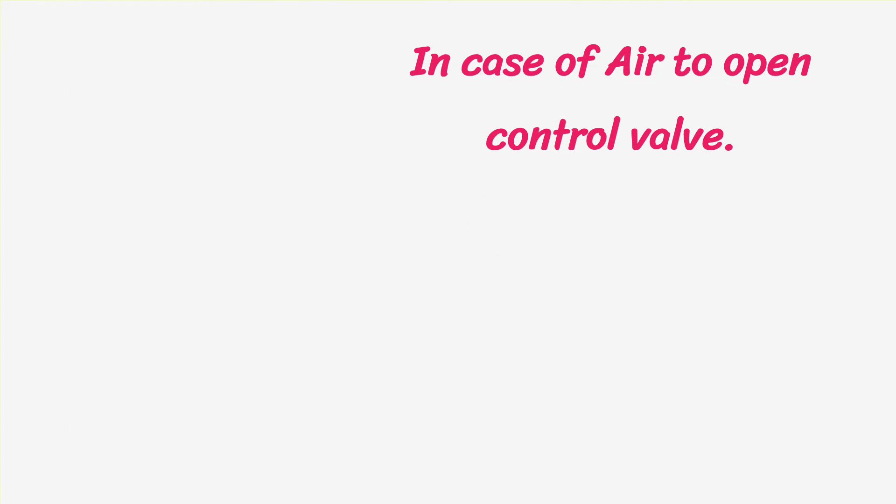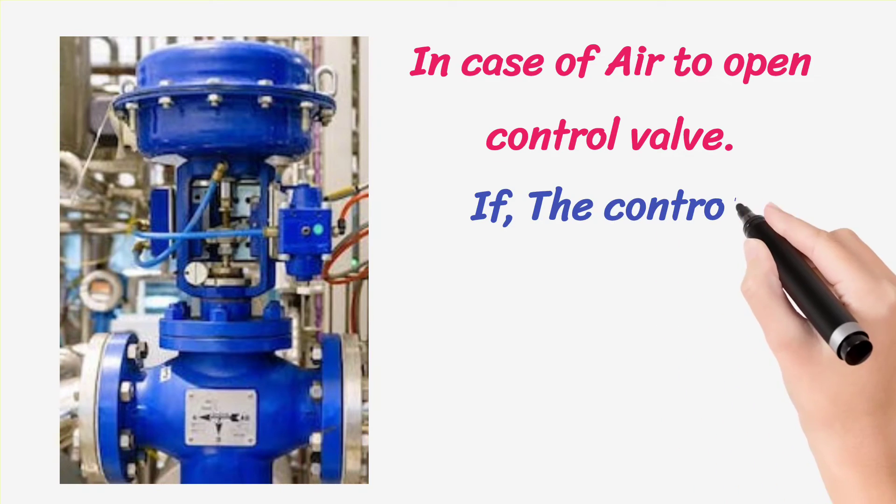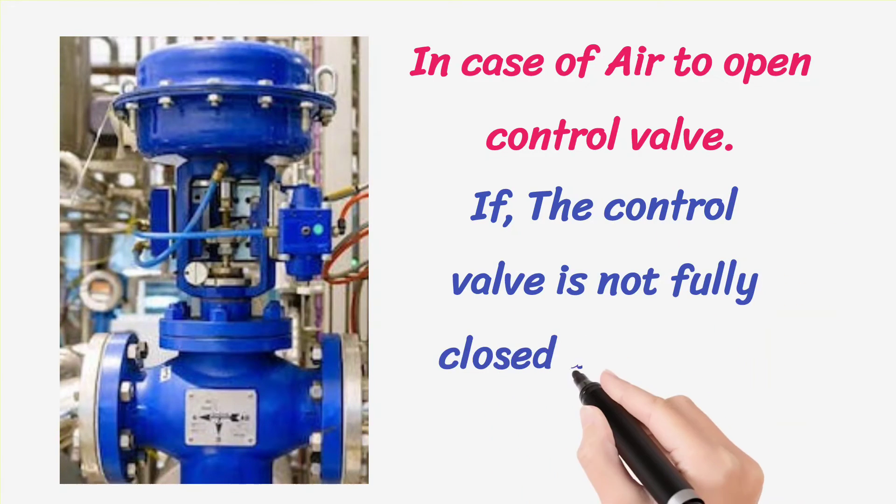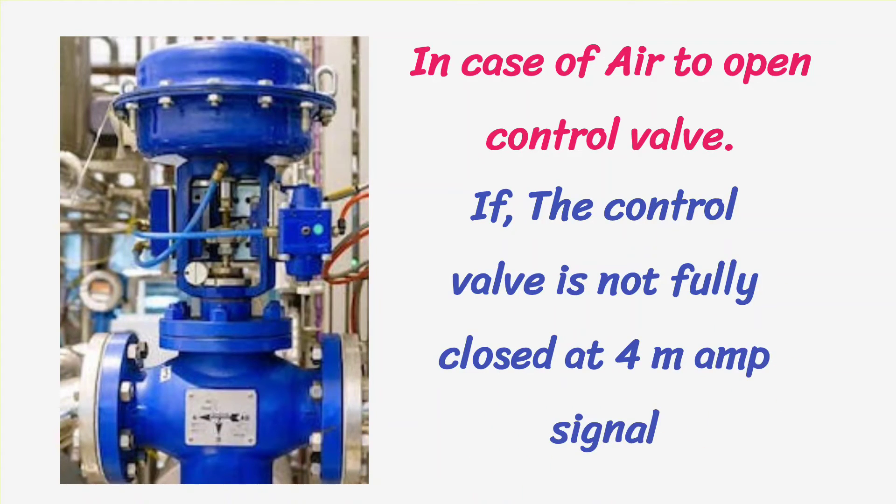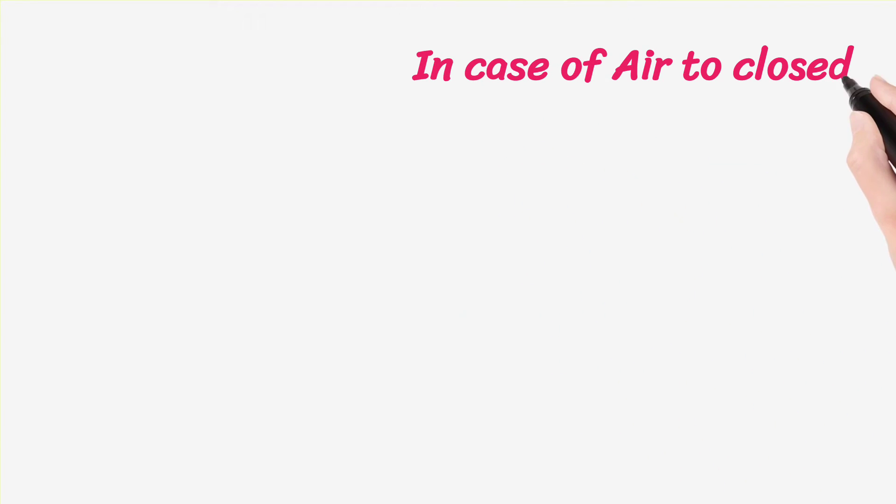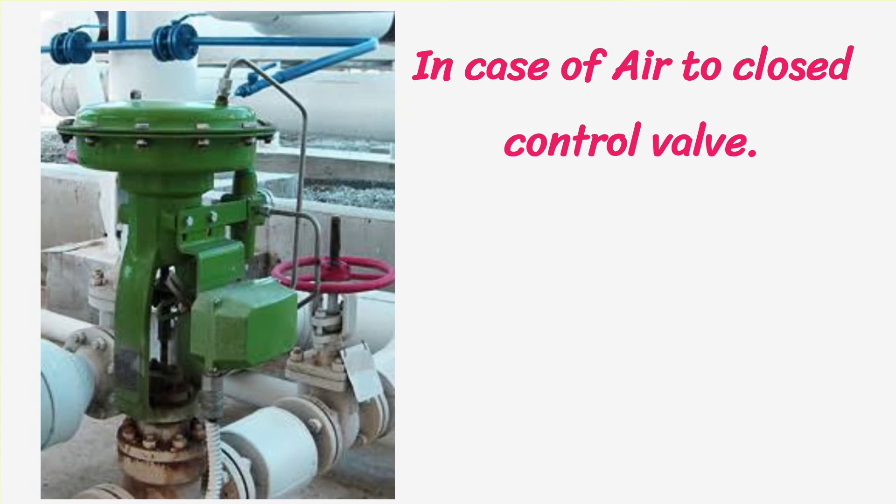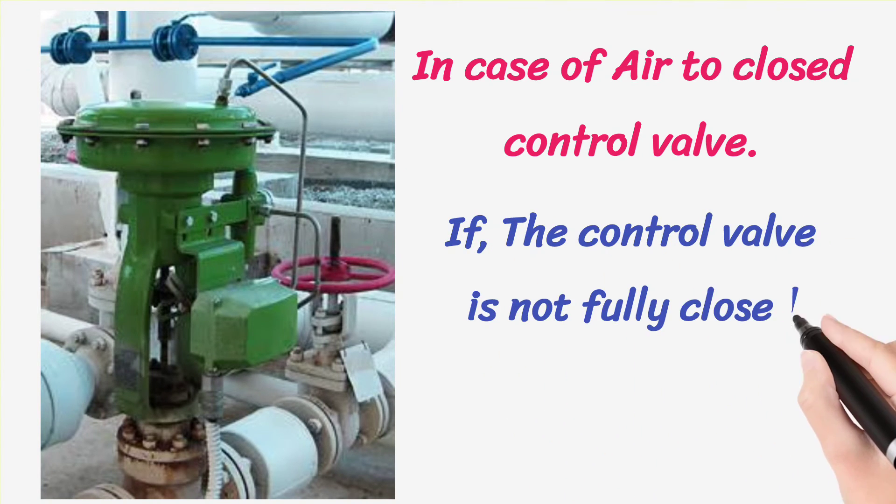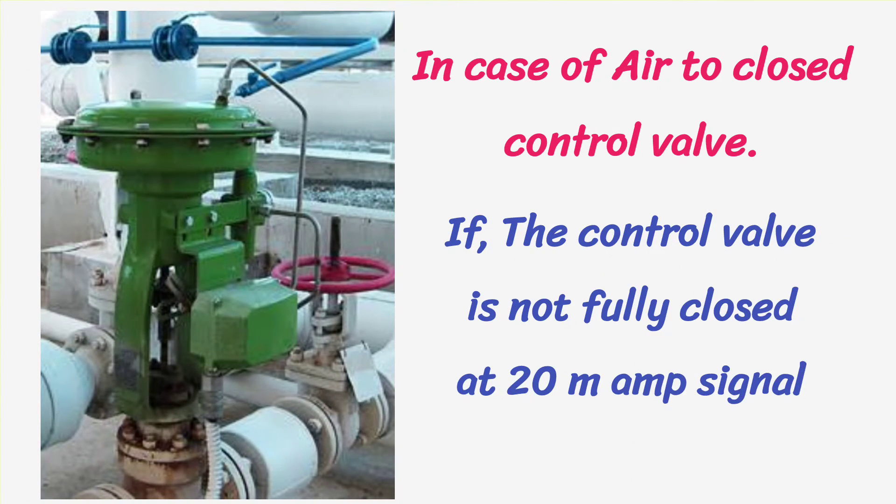In case of air to open control valve, if the control valve is not fully closed at 4 mA signal. And in case of air to closed control valve, if the control valve is not fully closed at 20 mA signal.